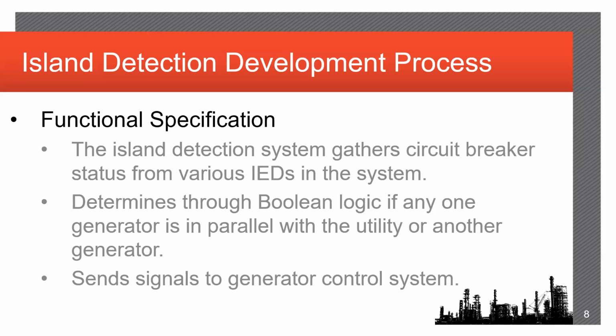So inside of the functional specification, the purpose of this is to gather circuit breaker statuses from all of the various IEDs in the system and determine through Boolean logic if any one generator is in parallel with the utility or possibly with another generator. And then once that determination is made, signals are sent from the island detection system to the generator control system to change control modes as necessary.